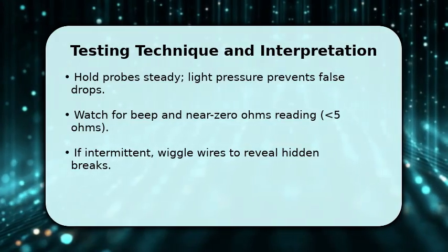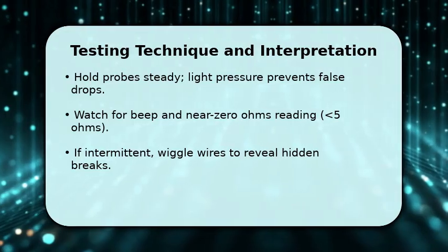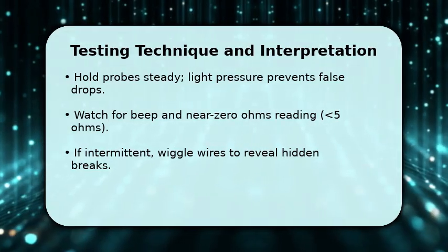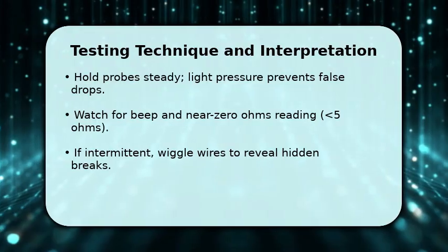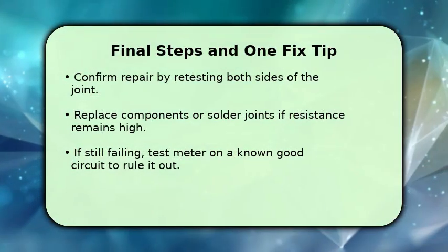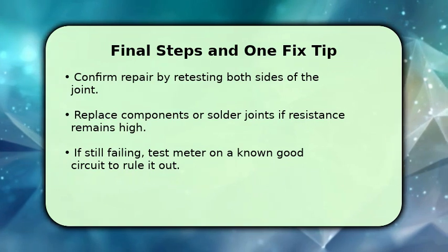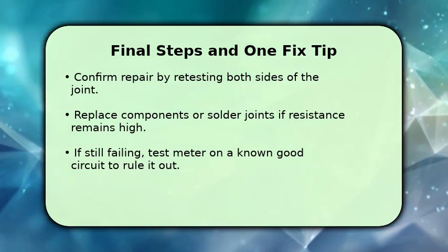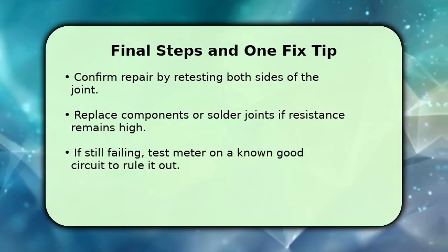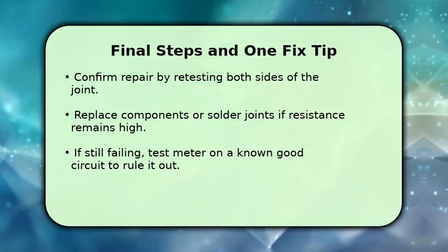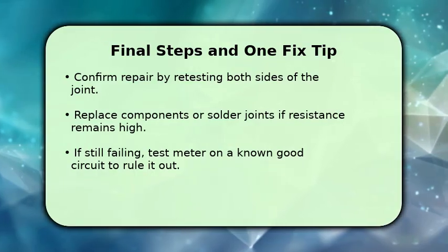Once you identify a suspect section, annotate it and repeat tests at adjacent junctions to isolate the exact breakpoint. After repairing or reseating the suspect connection, retest exactly the same points to confirm continuity is restored. Make sure you reapply the same probe positioning and pressure so your comparison is valid.